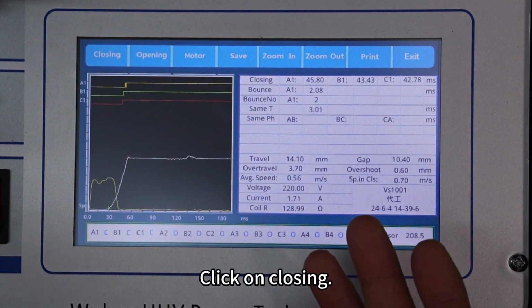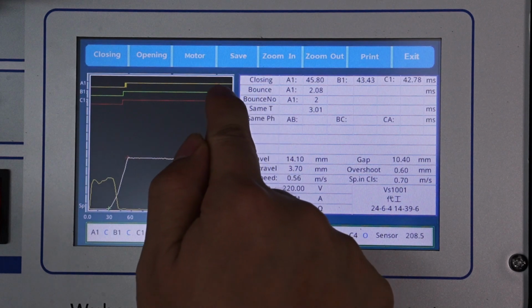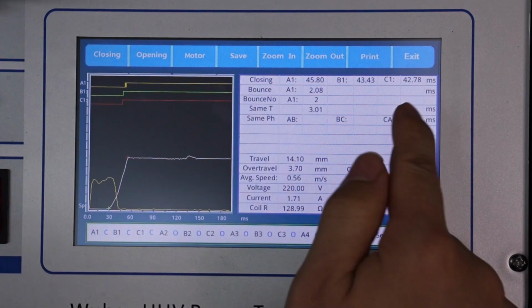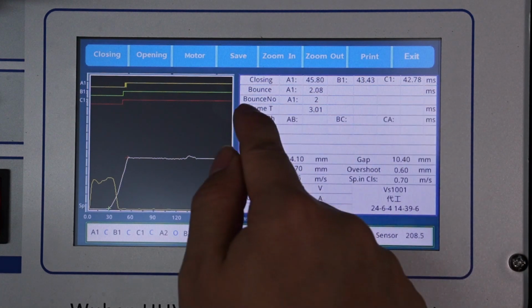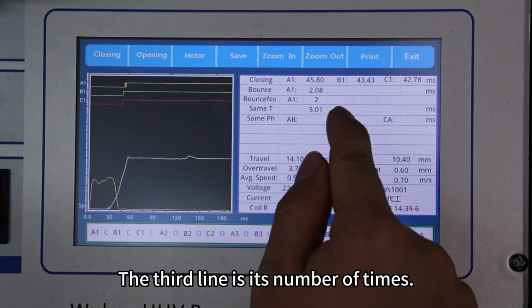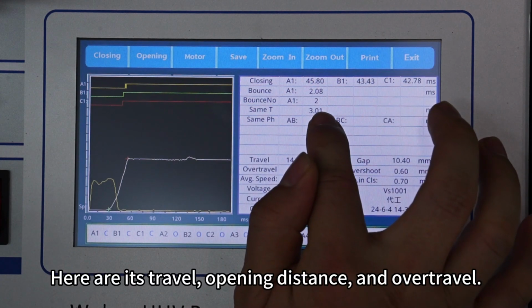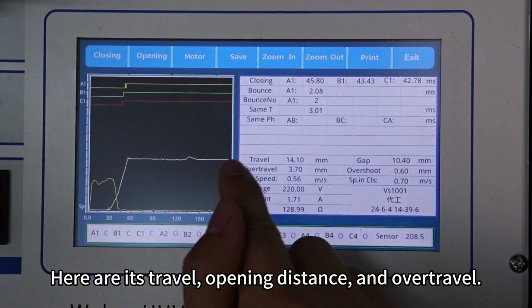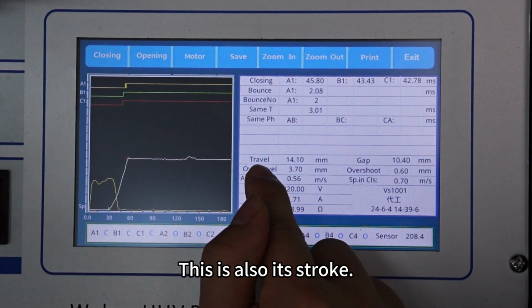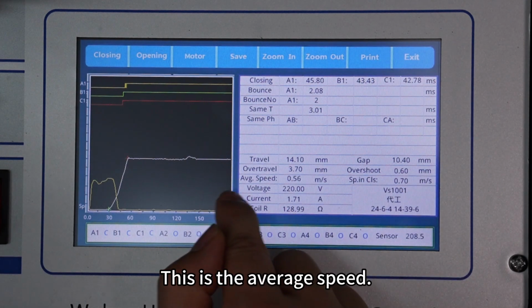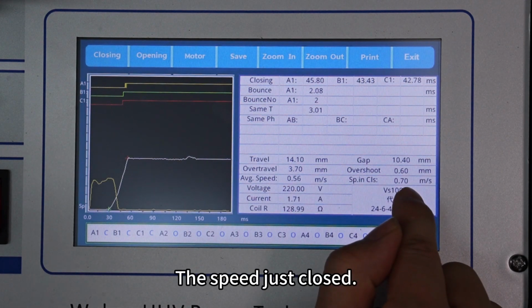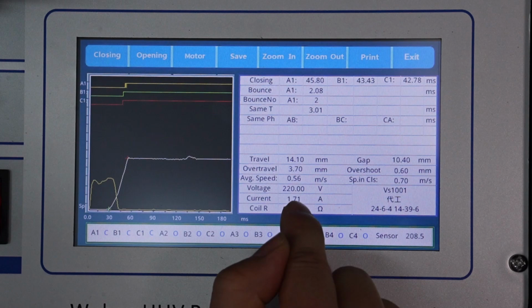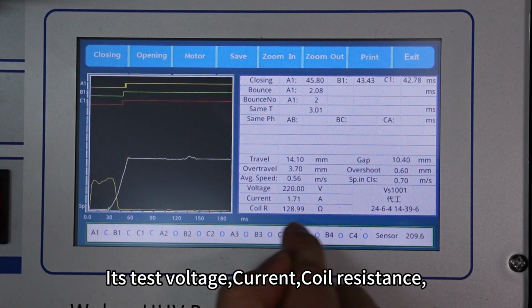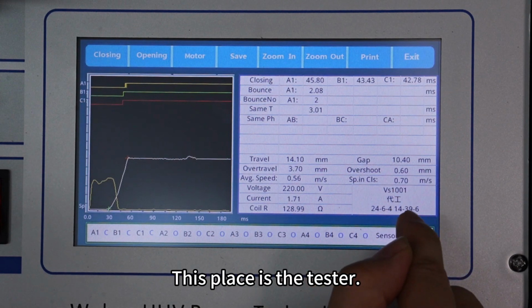Click on closing. You can see the data comes out. This is closing. Its time. The second line here is its bounce time. The third line is its number of times. This is its synchronization. Here are its travel, opening distance, and over travel. This is also its stroke. This is the average speed. The speed just closed. Its test voltage, current, coil resistance, this place is the tester.